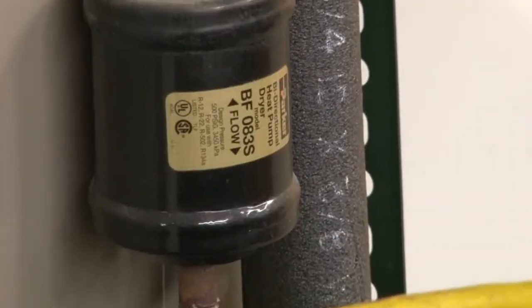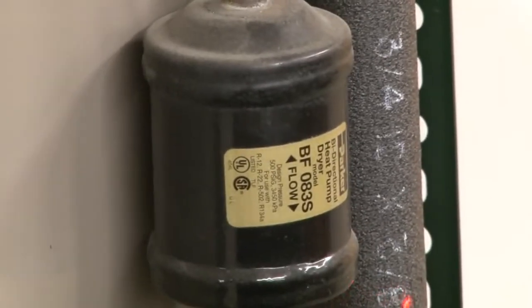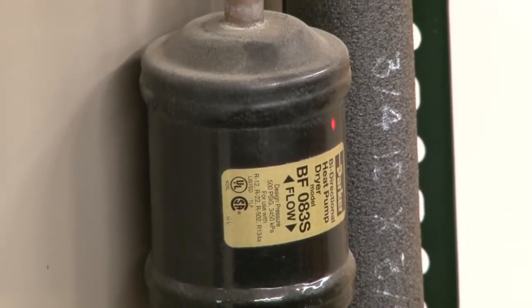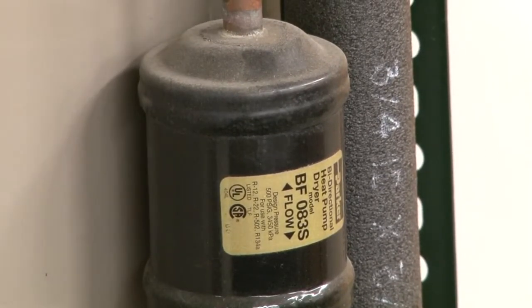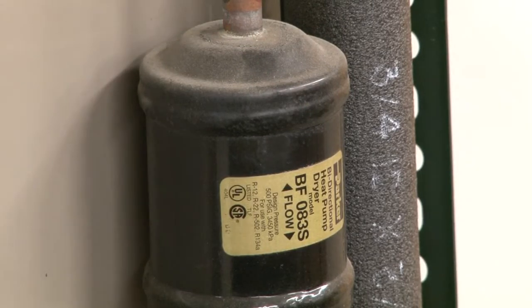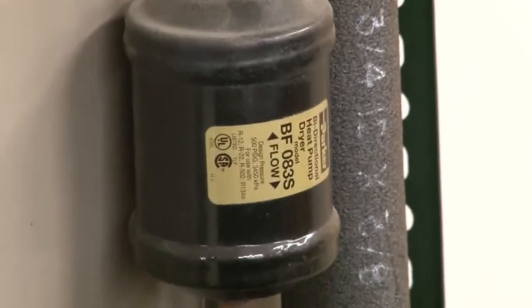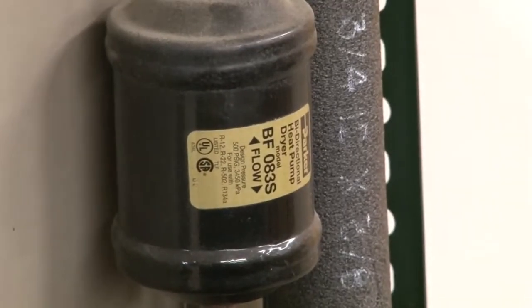We'll move on down the liquid line. We're going to see a filter dryer. That's designed to remove any type of buildup of oil, like any type of filter. It also aids in removal of anything that is not refrigerant inside the refrigeration system, any type of acid or moisture that's inside.